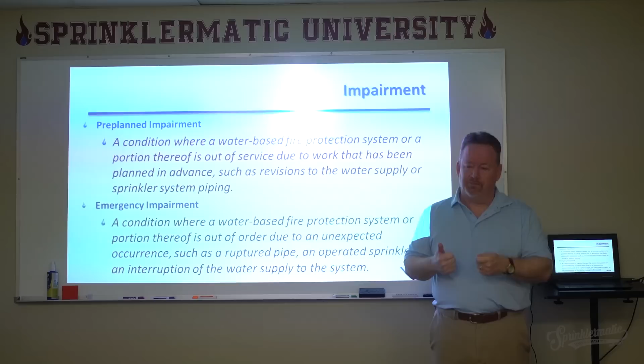An emergency impairment is where the protection of the system, or a portion thereof, is out of order due to something unexpected, like a forklift driver driving into your sprinkler, which wasn't expected. So the difference between a pre-planned and an emergency impairment really comes down to your reaction: if you say 'I'm going to shut this valve and we're going to do work on it,' that's a pre-planned impairment. If you say 'uh-oh, that wasn't supposed to happen, we better shut the valve,' that's an emergency impairment.